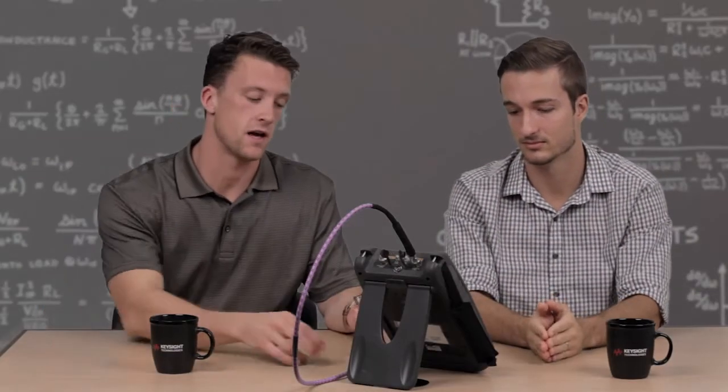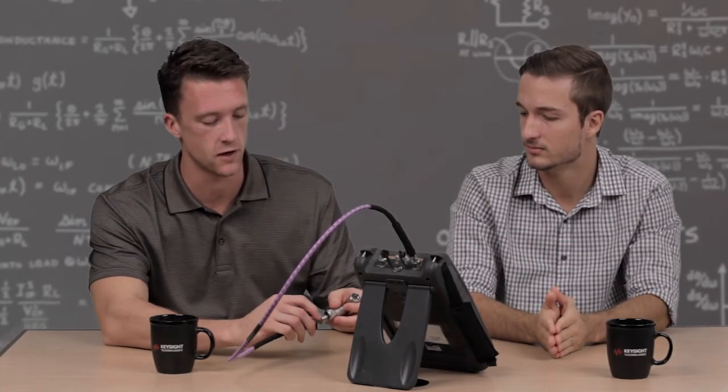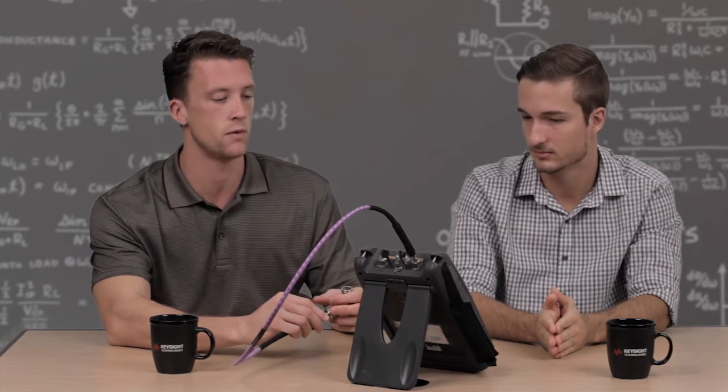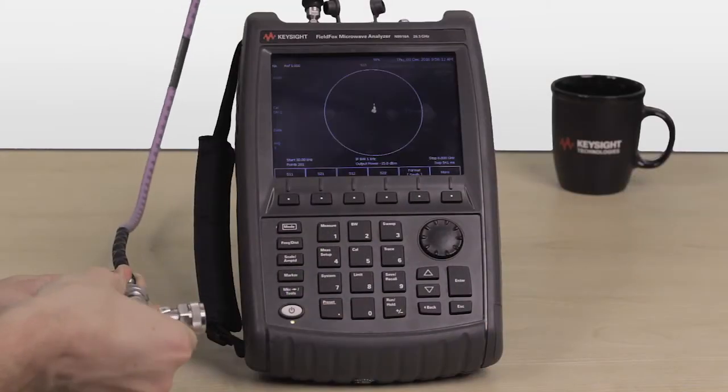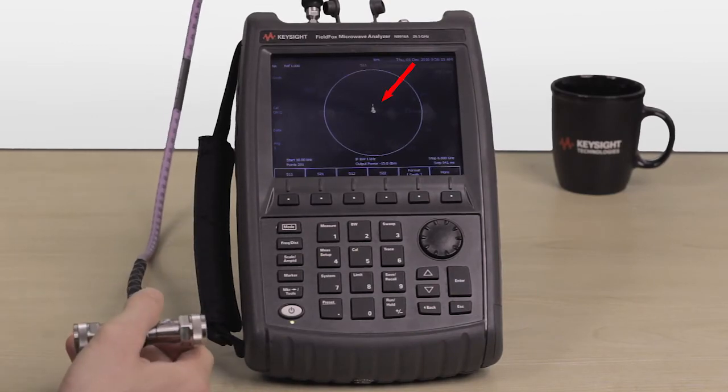And we can verify this calibration by hooking up a 50 ohm load to the end of the cable. And what we would expect to see on the screen would be a perfect match right in the center of the Smith chart. And that is exactly what we see.